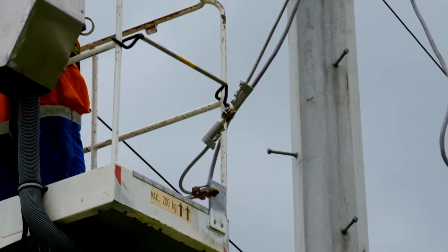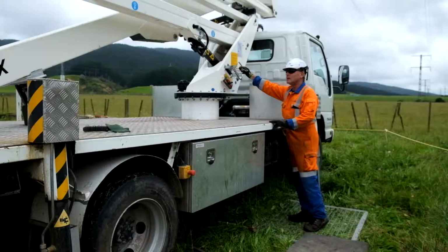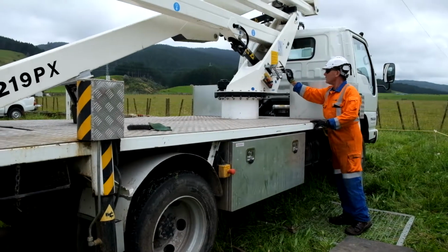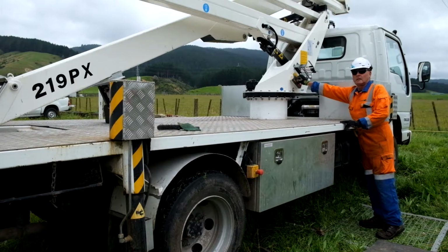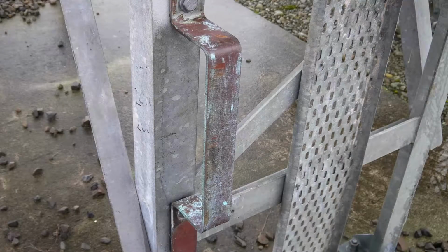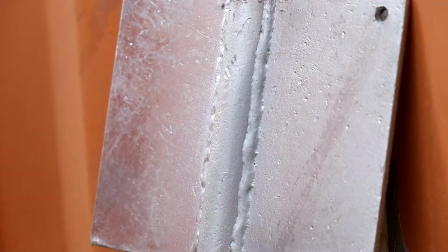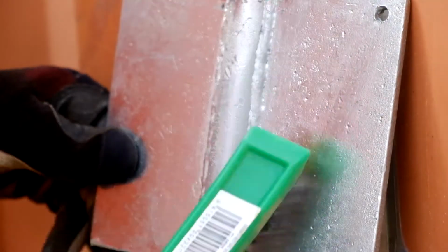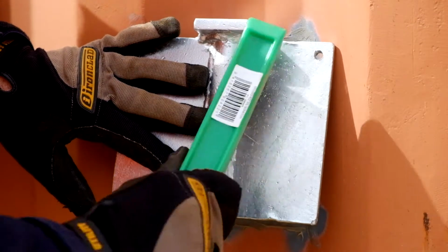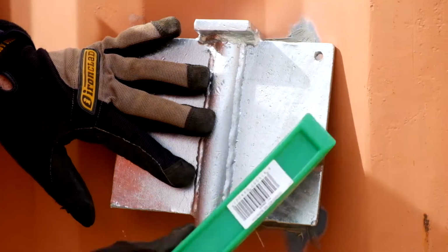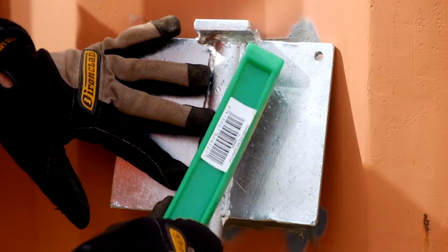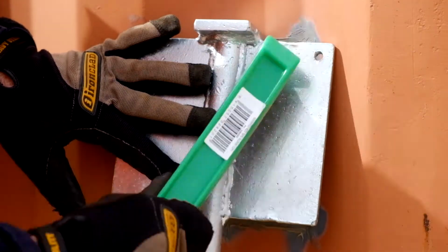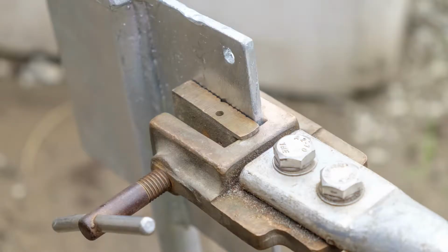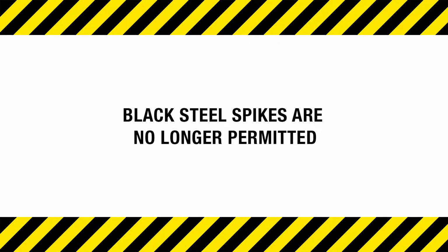Some of these earthing points can present themselves as galvanized steel, black steel, which may show red rust on the surface, stainless steel, and sometimes copper. All need to be cleaned to a bright, shiny surface prior to attaching a tail clamp. Where an earth stake is to be used, the contact surface where the tail clamp attaches should be free of contamination and brushed or buffed to ensure good conductivity. Earth stakes used on Transpower sites must be galvanized. Black steel spikes are no longer permitted.